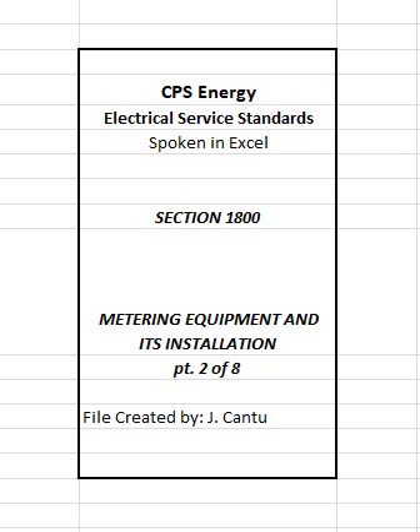All designs shall be submitted to CPS Energy for approval before installation. Note 3. Where customer's service design requires the use of a larger instrument transformer enclosure than those furnished by CPS Energy, customer shall submit to CPS Energy for approval an enclosure meeting CPS Energy's specifications and construction criteria. D. Standard transsockets. Transsockets are self-contained, weatherproof metering enclosures that house all required instrument transformers, test switch, metering control cable, and meter socket.